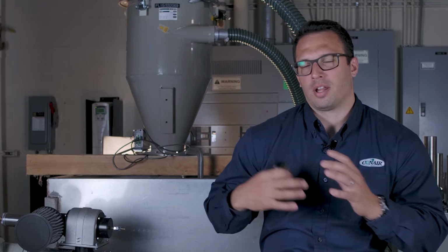In order to control pneumatic conveying systems, in most cases you only have to deal with digital inputs and outputs, but on some of Conair's equipment we also have the requirement for analog inputs and outputs. So digital inputs and outputs, or digital I/O, are essentially a 0 or a 1, or a yes or a no, or what I always like to call a light switch, where you fire an input or an output or you don't, based on what your software tells that input card or output card to do.